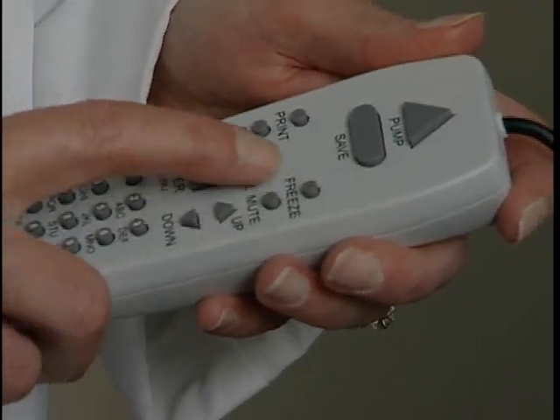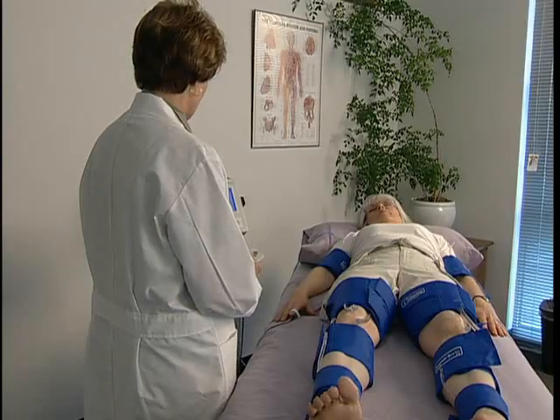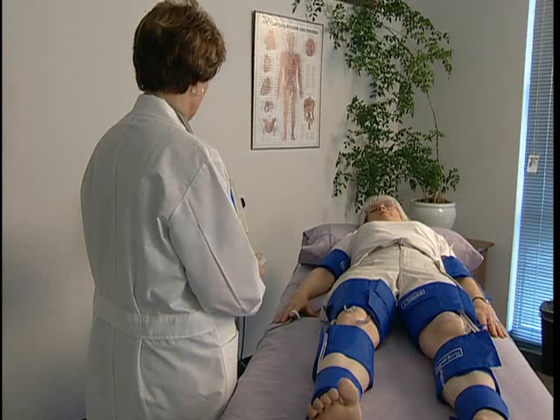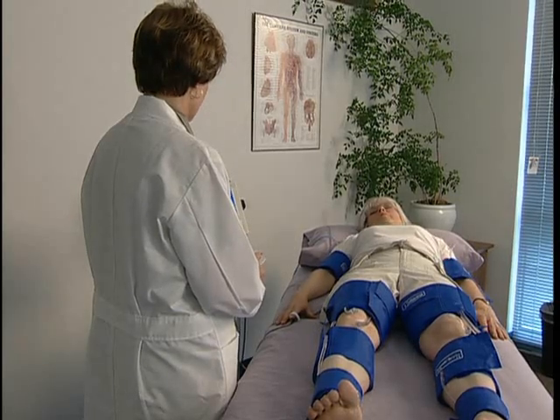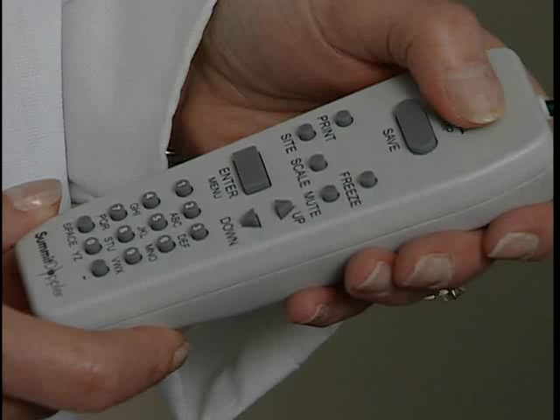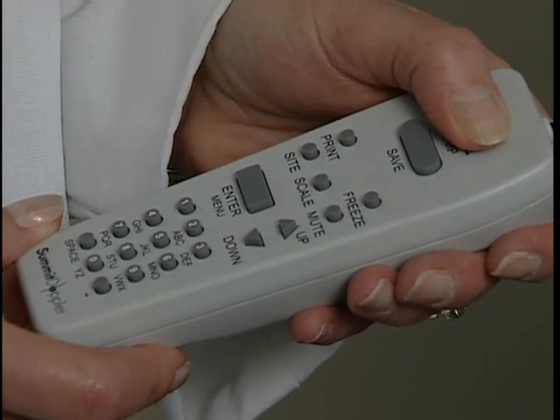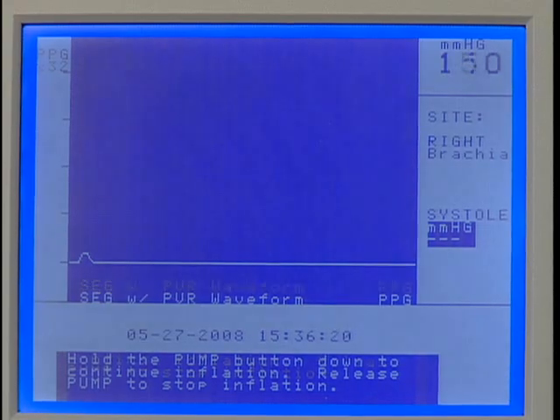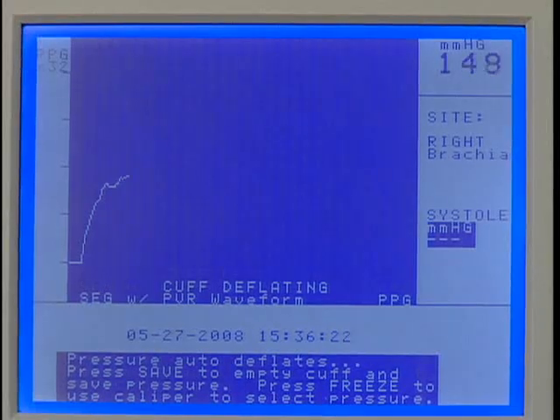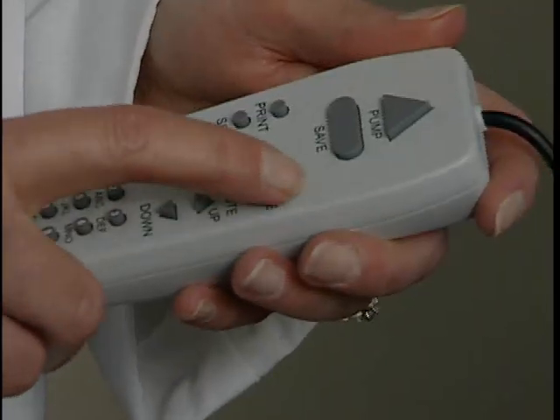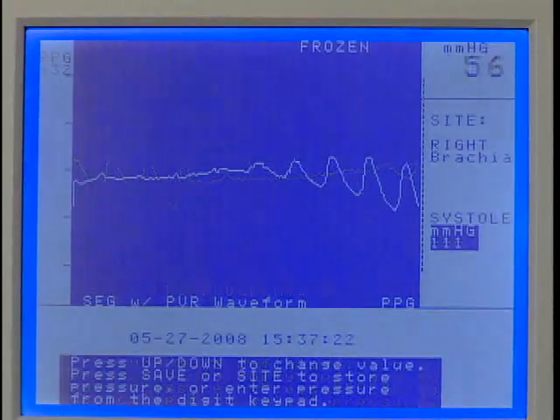Press Scale 1 or more times as needed to adjust the vertical scaling to obtain a waveform as large as possible without clipping at the top. Once the waveform is stable, press Pump to inflate the cuff until the PPG pulsations disappear. Release Pump and the cuff will begin to deflate. Press Freeze after several pulses have reappeared.